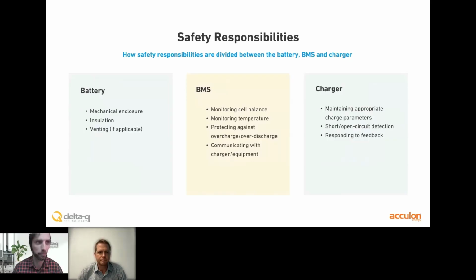So back to the safety point, I just wanted to touch on how everything in the system has some responsibility for maintaining safety, with redundancies between those elements. Just to go over the basics: the battery itself is a mechanical enclosure that encases all the cells, making sure there's insulation between the electrolytes. Certain batteries will vent off electrolyte when it starts boiling, and the battery needs to be able to swell with heat without the case cracking. So we want that to be robust and reliable.